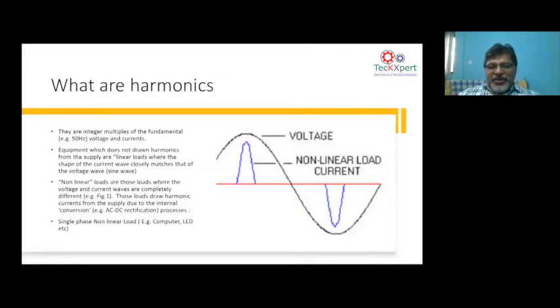Now we come to our subject of harmonics. This is a topic which is going to be given a lot more importance than the rest of the power quality problems which I just covered a little earlier. Now harmonics, everybody will be knowing, it is multiples of the fundamental frequency. That's the simplest definition you can give for harmonics. If your fundamental frequency is 50 hertz, the odd and even multiples are 50, 100, 150, 200, 250. These are all the integer multiples. So that is how harmonics is defined.